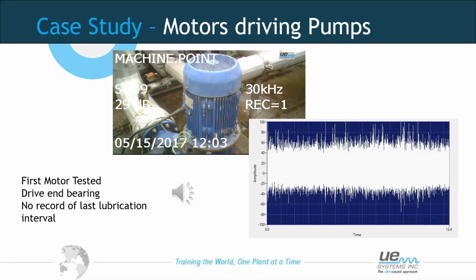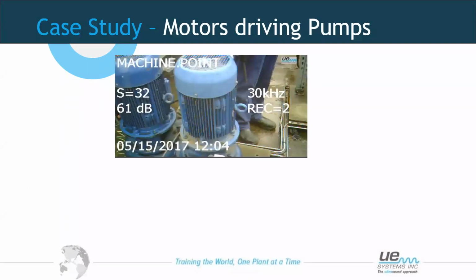So going on to the case study again. We checked the first one. We had a good sort of comparison method to actually employ here. So we went to the second motor, and again, looking at predictive technologies, we're using the same point, the same frequency to make sure we get a good comparative reading. We checked it on the same point of the drive end bearing of the motor, and we could see quite clearly that we had a large increase in decibel value.